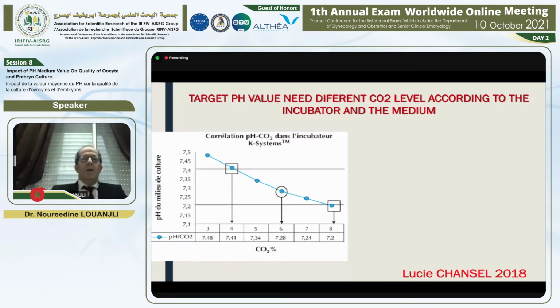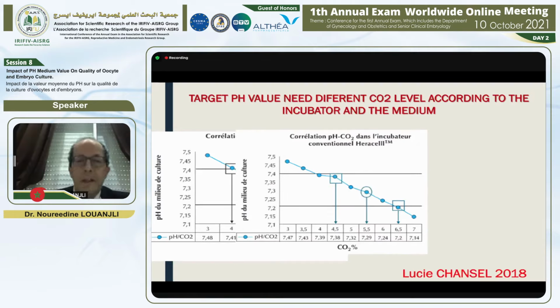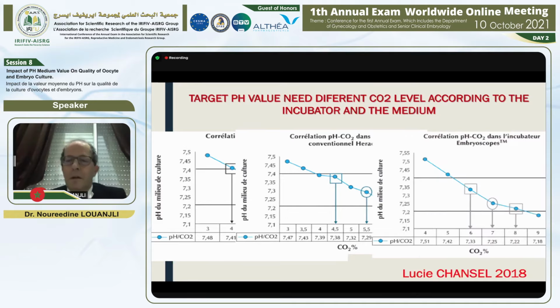Equally, the value of pH depends on the incubator and the media. If you work with an incubator, you have a target value of 7.3 for pH. If you change the incubator, you have to recalibrate with the new incubator. For example, in this condition with the same target, we need 6 for the first incubator, 5.5 for the second incubator, and perhaps 7 for the third incubator for the same pH target. We have to calibrate according to the new incubator for the same medium.